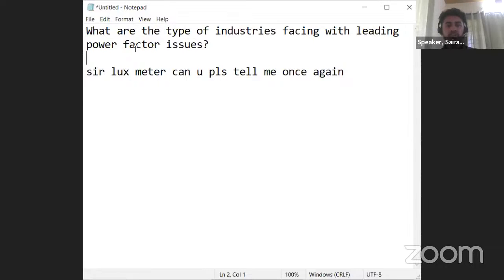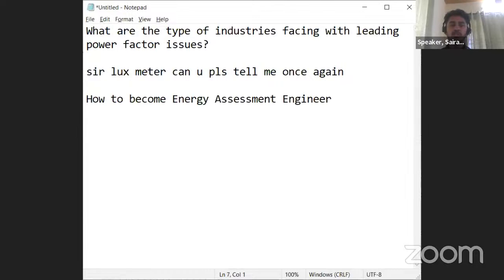The leading power factor industries, as we came across, I have witnessed the leading power factor issue in the textile industry, where they have installed capacitor banks on the higher side, rather than the required amount, they have increased the capacity of the capacitors, and also the sensing problem was the issue. Usually we take feedback from a single phase for the automatic power factor controller, but due to the unbalances in the three phases, we can't match the power factor with respect to the feedback from the single circuit. If we could go for three phase sensing, then we can properly control the power factor issue.